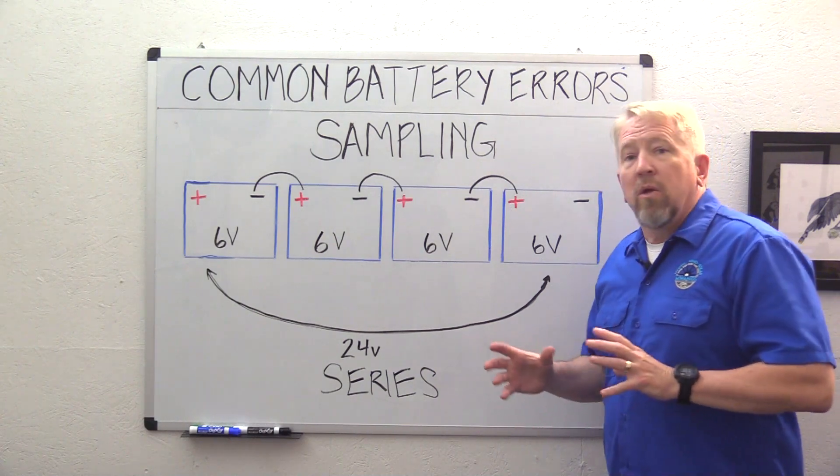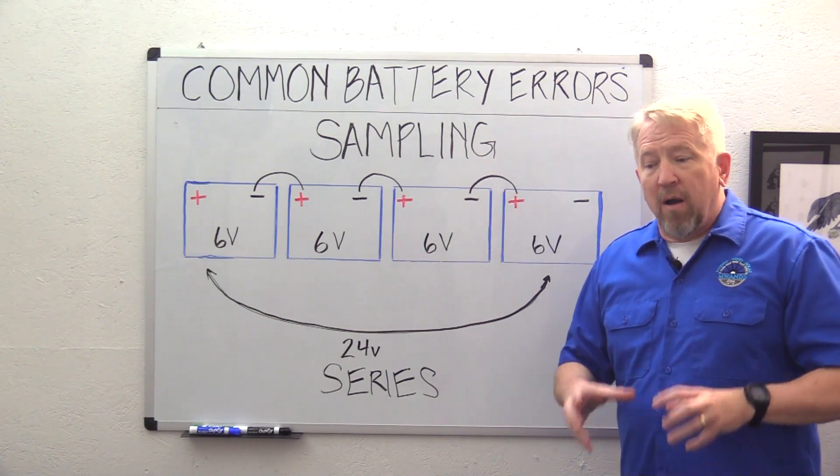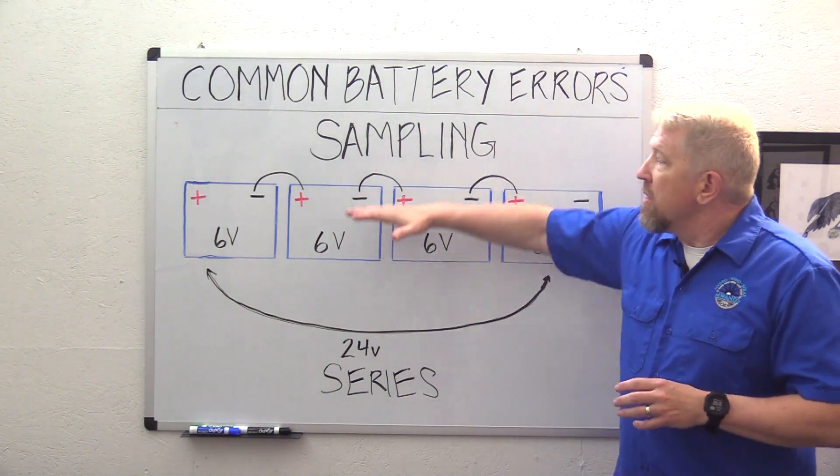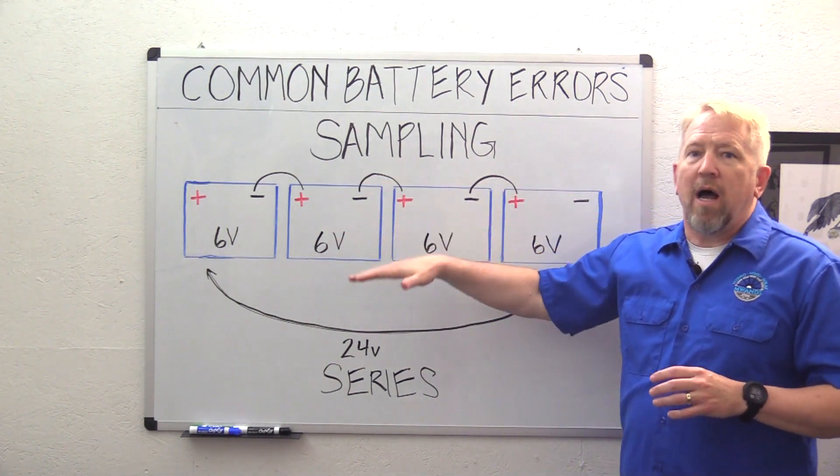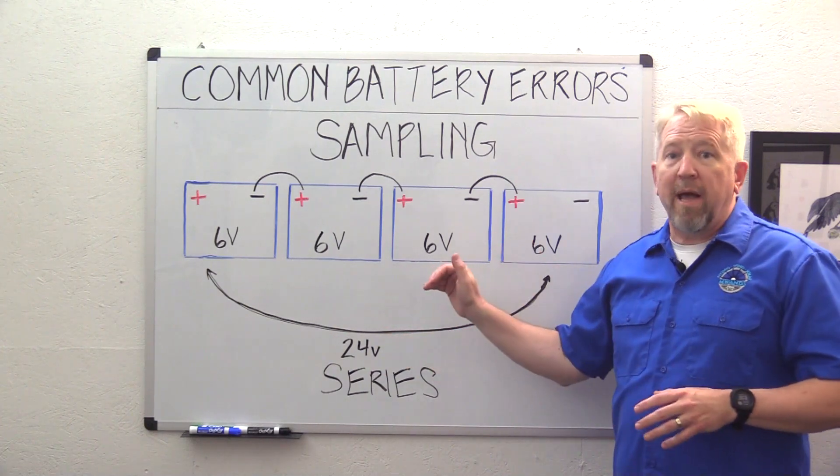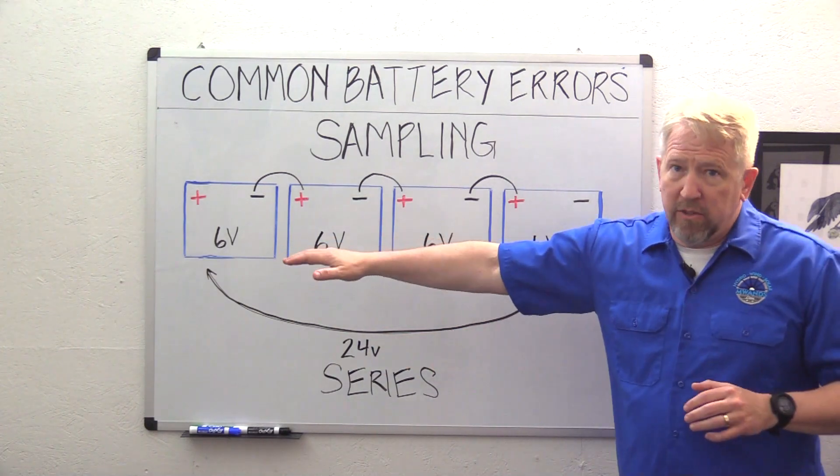And we end up hurting this battery. We always want to remember too, when we have a battery problem, when we hurt a battery that's in a series like this, then our whole series drops to that lowest common denominator on the battery. So our worst battery is what all of our batteries do.